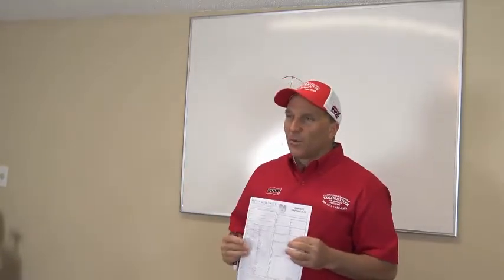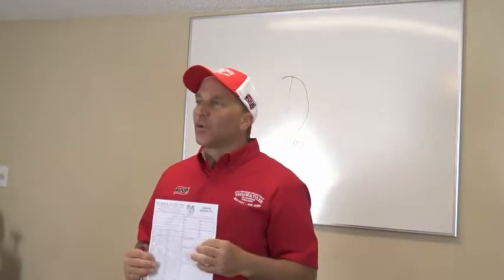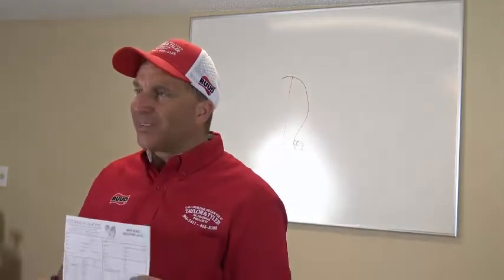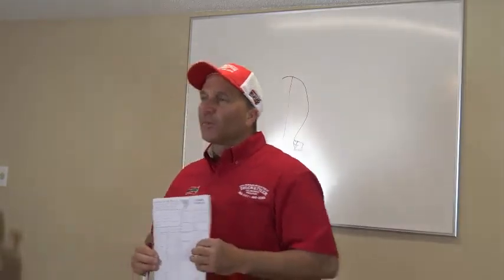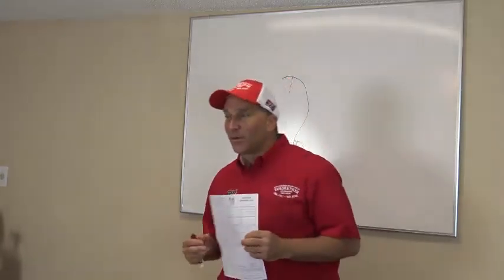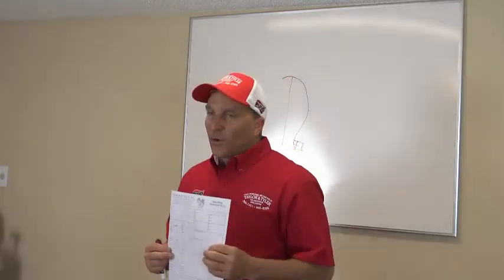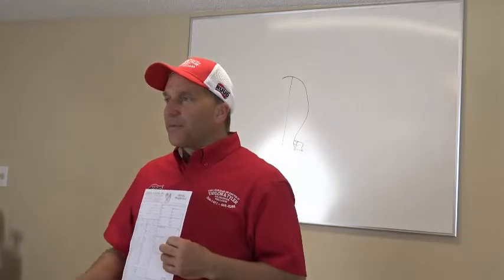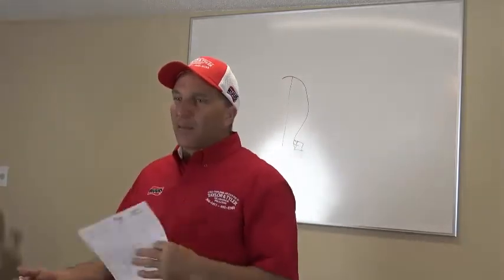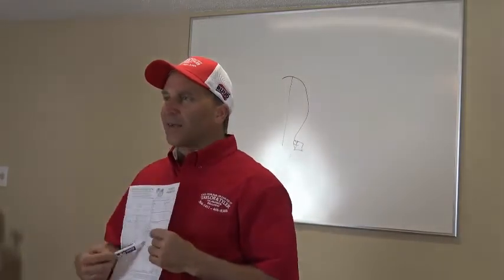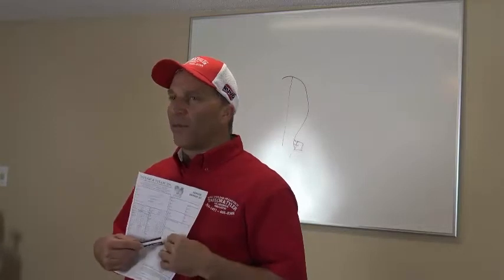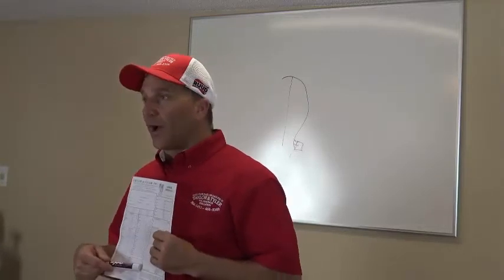So what is normal? What's your normal delta T? 18 to 20 degrees. What's your normal subcooling? 10 to 12 degrees. What's your normal superheat? 12 to 15 degrees. Well, go to look at your condenser, and it says, on this particular condenser, I'm making up 85 degrees outside, head pressure, 285 pounds. What is yours? 255. Well, something's wrong.